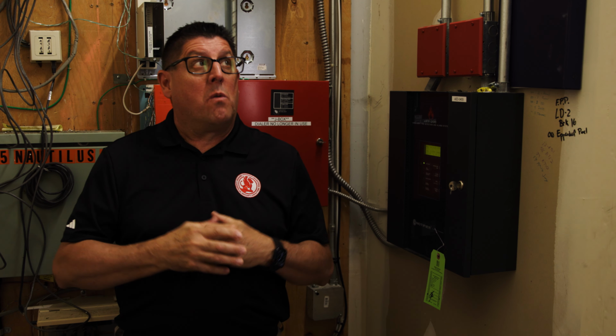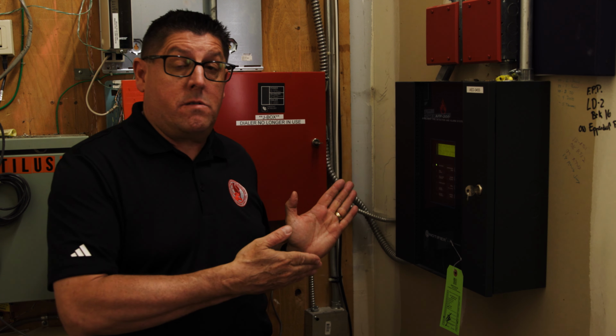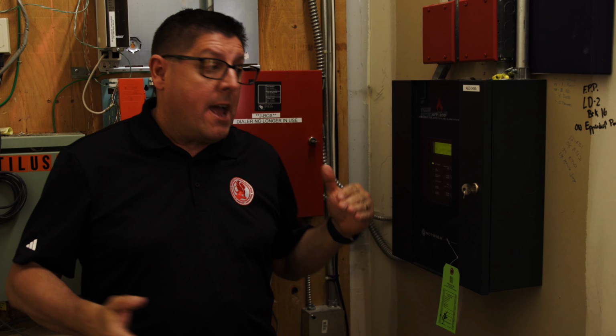Fire alarms are an essential part of the life safety inspection. While not every building has a fire alarm, our ComSop says we are first to note the presence of a fire alarm system. The accessibility requirements for an alarm panel are the same as for any other electric panel. We should have 36 inches deep as well as 30 inches side to side. So make sure that all panels are accessible.